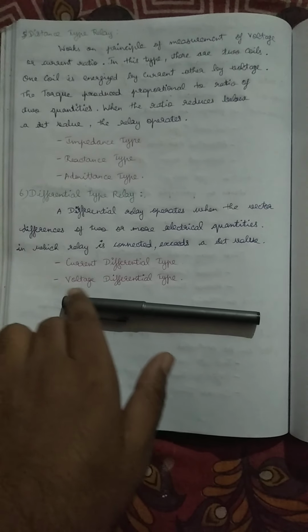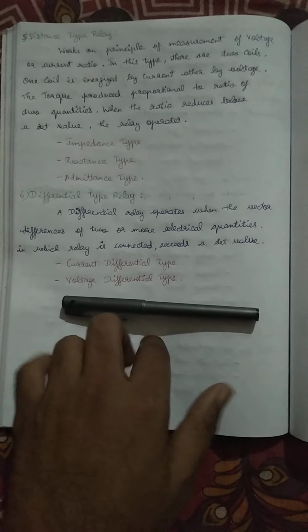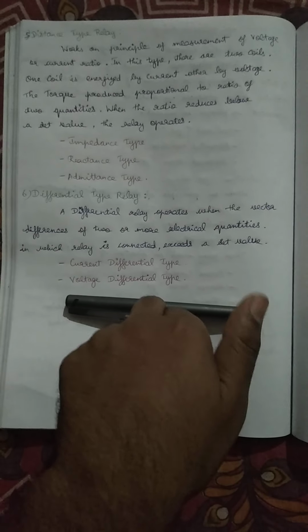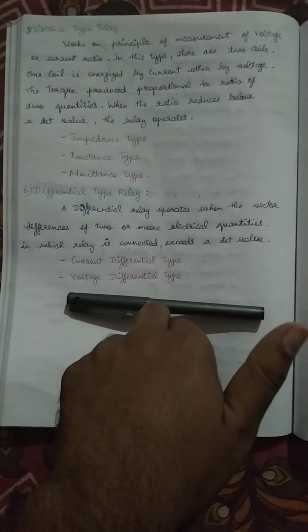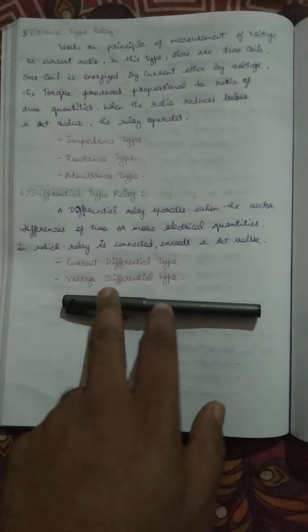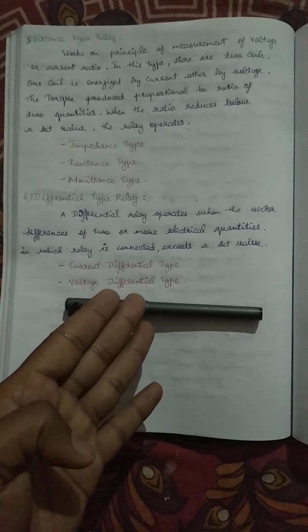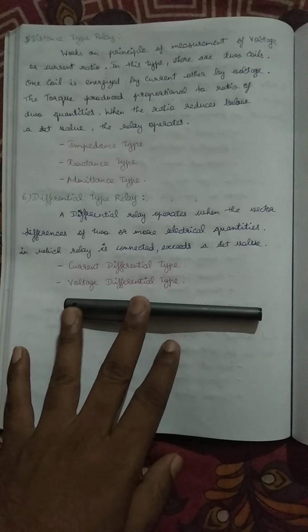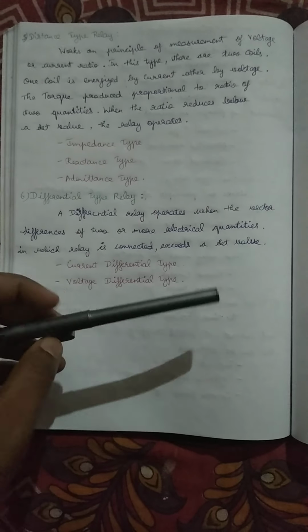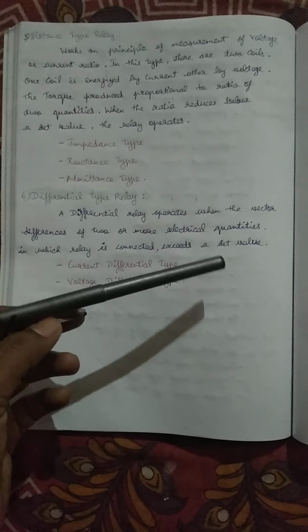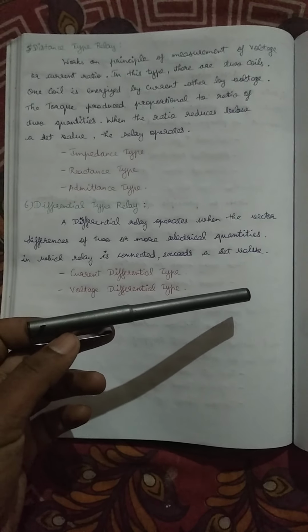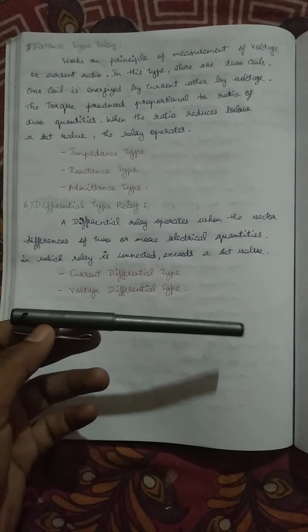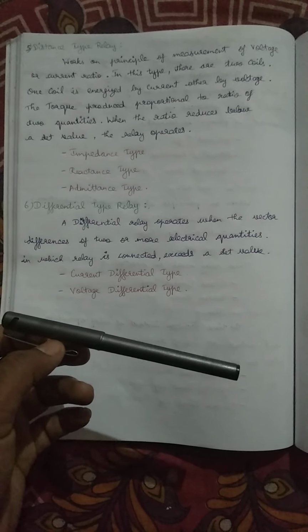The current entering goes in here, and there is no outgoing path. At that time, the relay automatically senses it and the unbalanced current is added as fault current, and it exceeds the set value of our differential settings, and automatically our trip will be initiated as a differential trip.